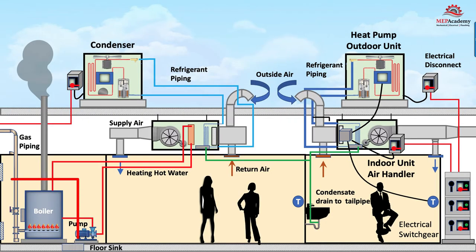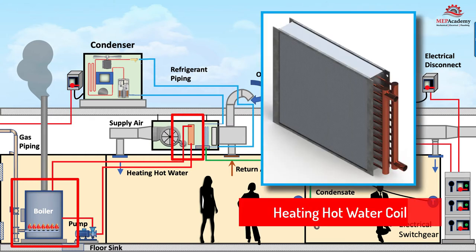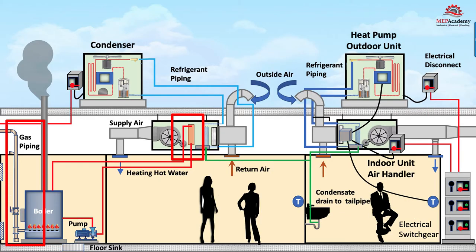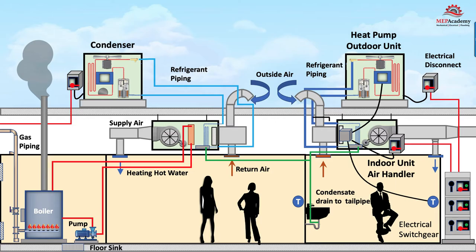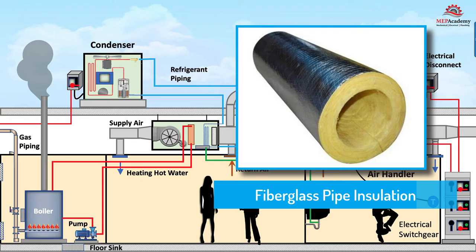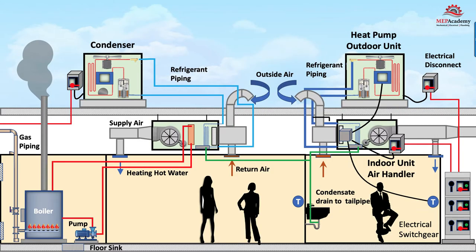Another option is to use a boiler to provide heating hot water to a coil located inside the air handler. The boiler will need a source of fuel for combustion, in this case natural gas. The heating hot water will need a pump to circulate the water to all of the air handlers in the building. Here we only show one air handler getting heating hot water, but it could also be dozens more in larger buildings. The heating hot water piping will need to be insulated, most likely with fiberglass pipe insulation to prevent the loss of heat from the pipes. Not shown is make-up water or other accessories like expansion tanks. This could also be a steam boiler with a steam coil in the air handler to provide heating.